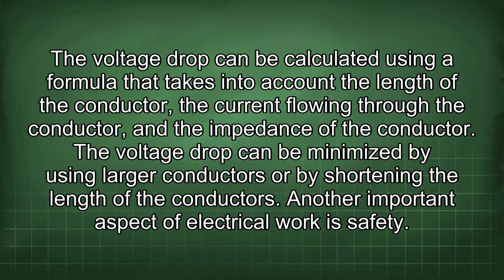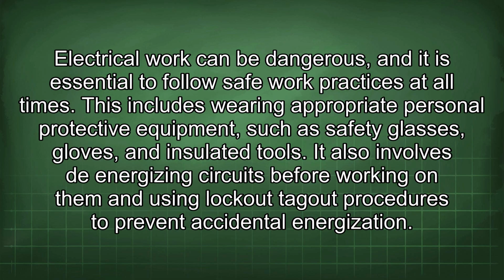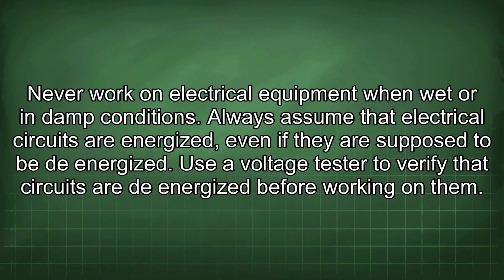Another important aspect of electrical work is safety. Electrical work can be dangerous, and it is essential to follow safe work practices at all times. This includes wearing appropriate personal protective equipment, such as safety glasses, gloves, and insulated tools. It also involves de-energizing circuits before working on them and using lockout-tagout procedures to prevent accidental energization. Never work on electrical equipment when wet or in damp conditions. Always assume that electrical circuits are energized even if they are supposed to be de-energized. Use a voltage tester to verify that circuits are de-energized before working on them.